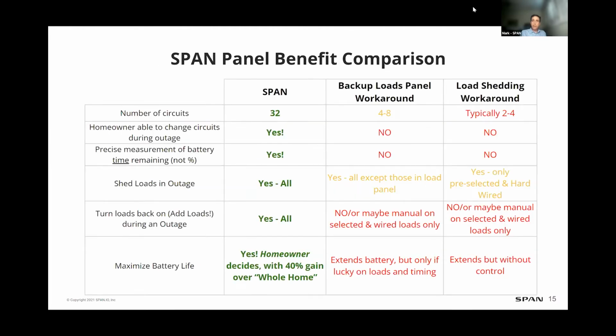This kind of gives you a feel for how different it is to use SPAN versus a typical storage system. With SPAN, you'd have all 32 circuits available to the homeowner. Typically, in a backup load panel workaround situation, you're going to pick anywhere from 4 to 6 to 8 circuits.